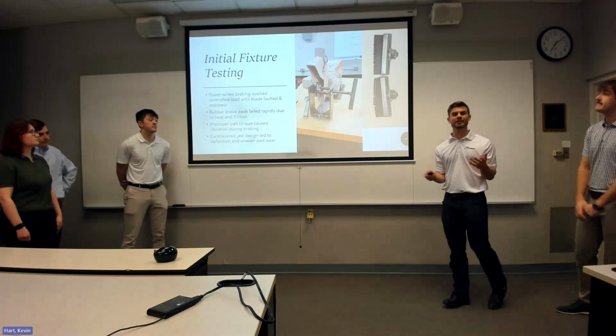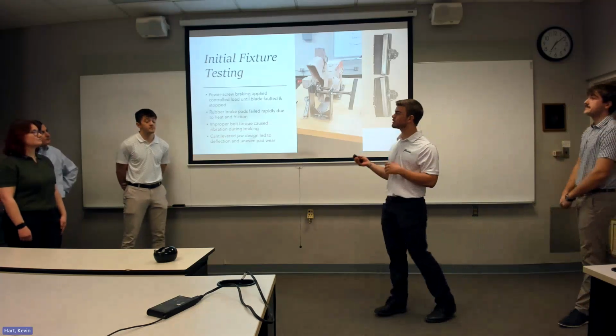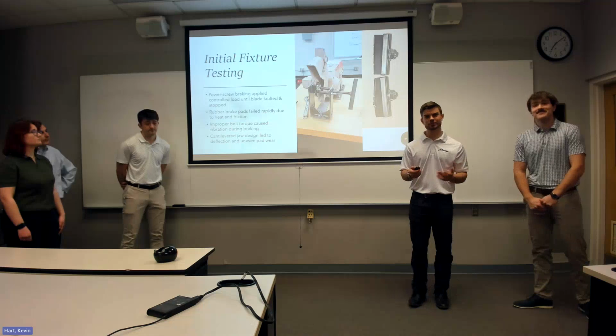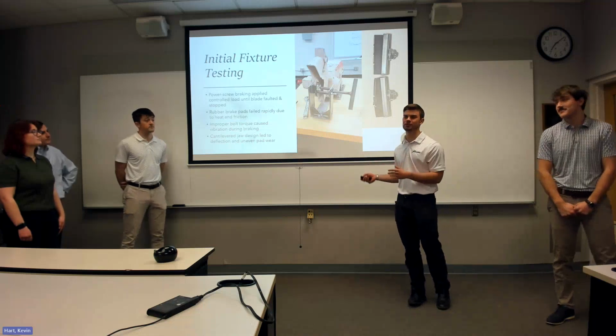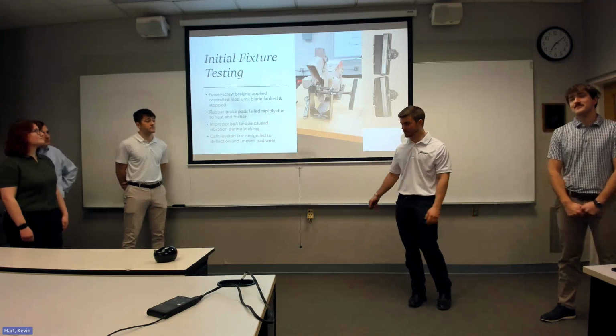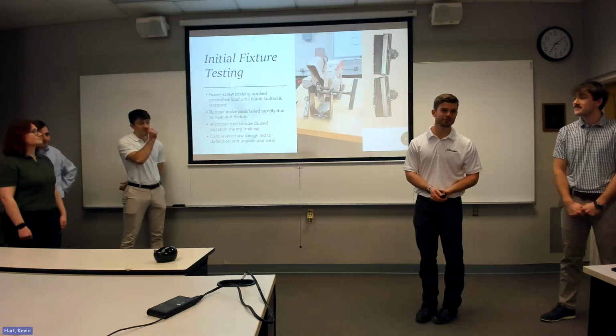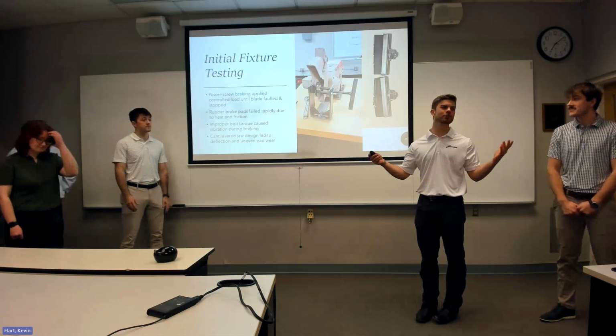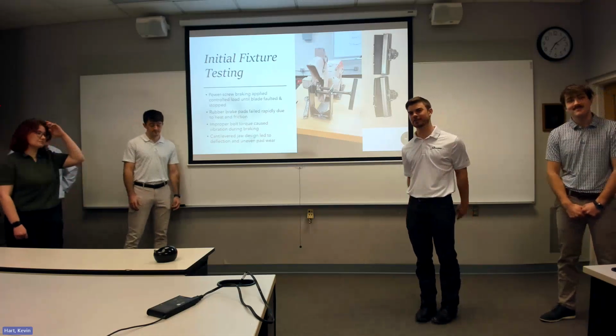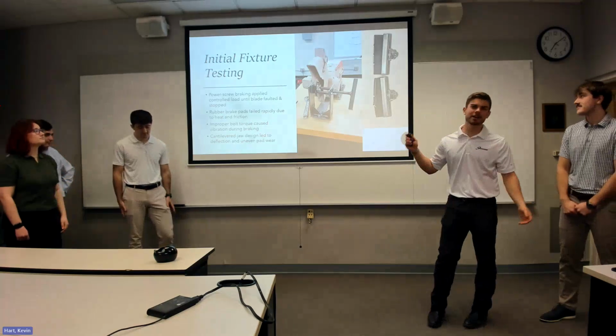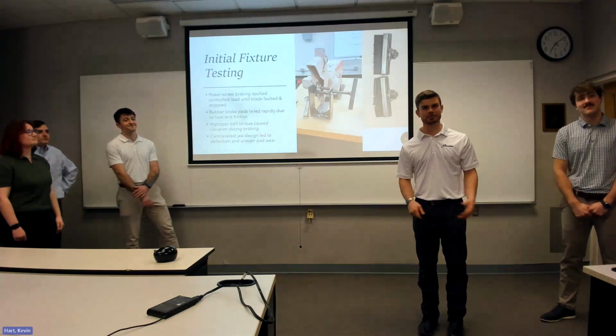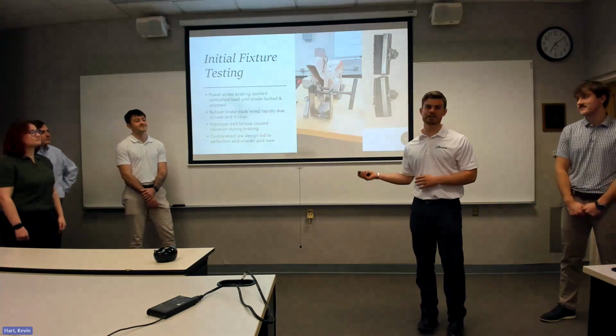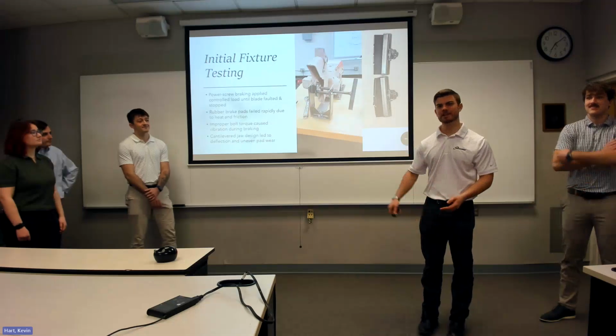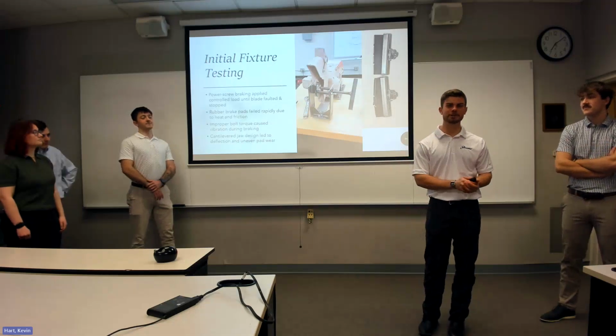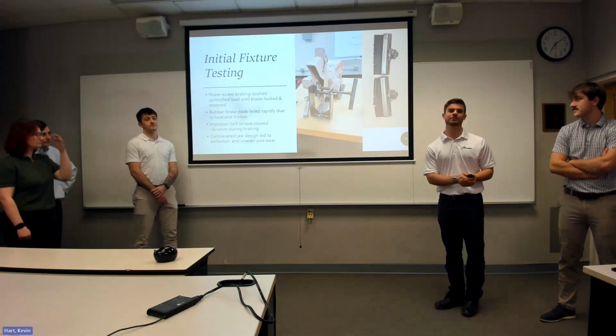So now we're going to put that test procedure to use. Initially, our first testing was to answer the question, does our test fixture work as designed? And there's 3 big takeaways that we learned from this test. Yes, we were able to overload the saw as intended, but our braking pads were not able to withstand the force of the blade. And then another takeaway is that there was excessive vibration in our braking mechanism.